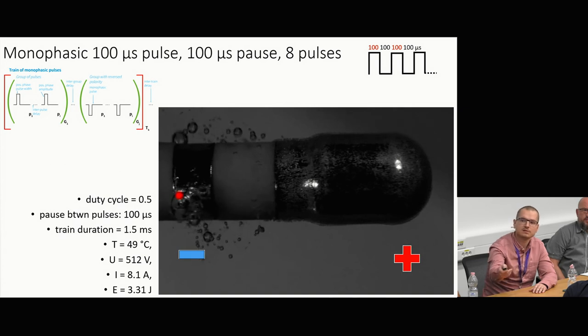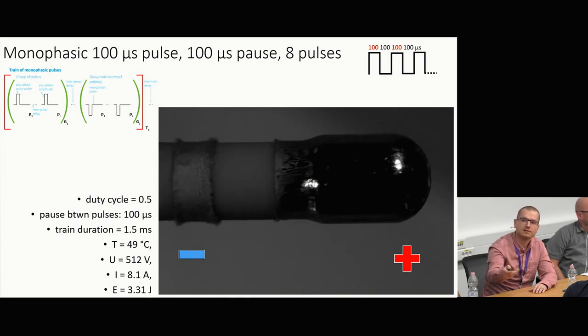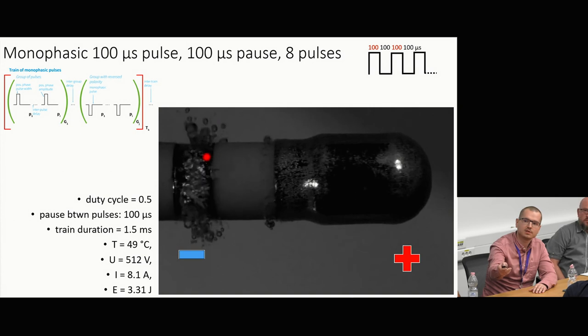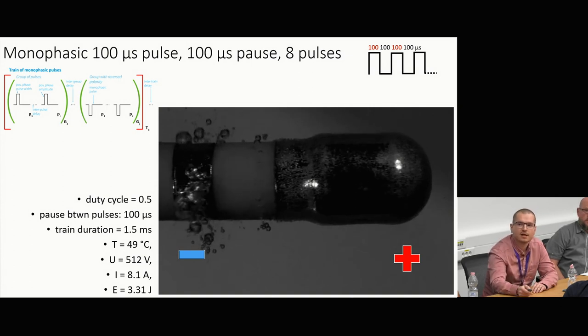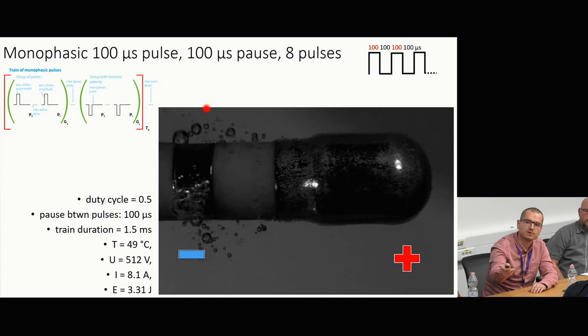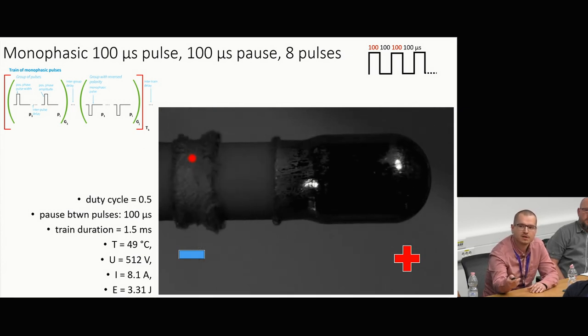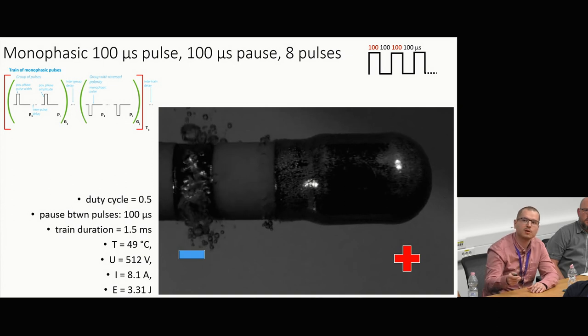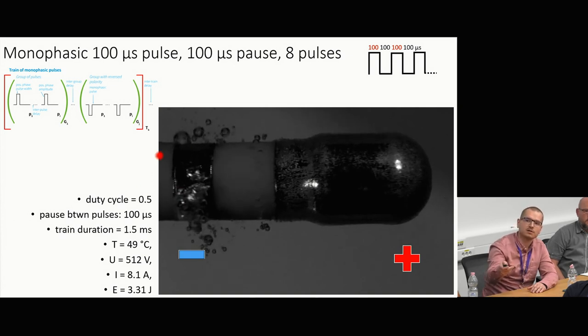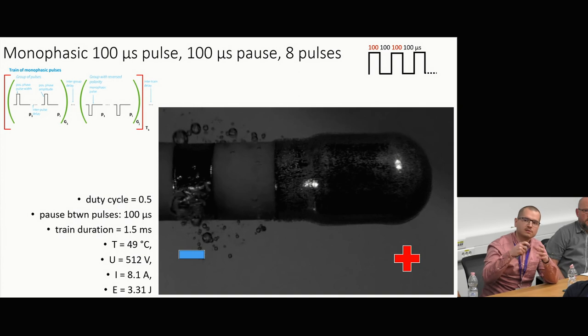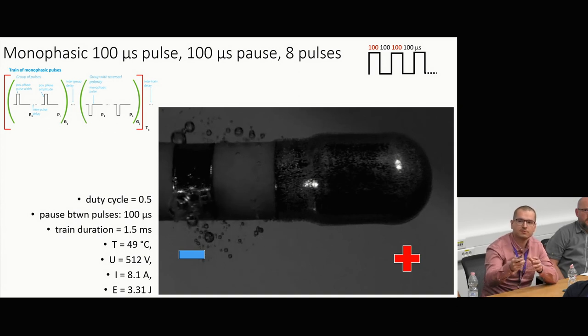What you see is boiling at the electrode edges where the current density is highest. When the pulse delivery is over, this water vapor that appears immediately implodes, causing an implosion that forces these bubbles, which were otherwise electrochemically generated, together, and they coalesce into larger bubbles and are blown away from the electrode surface.